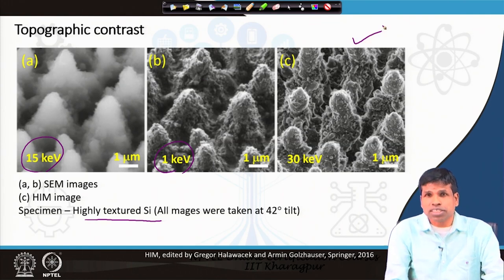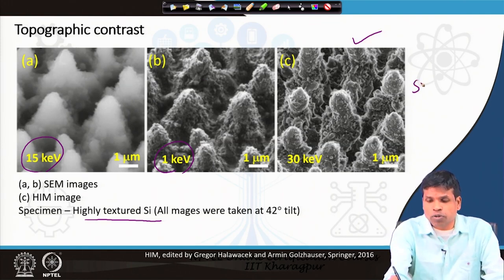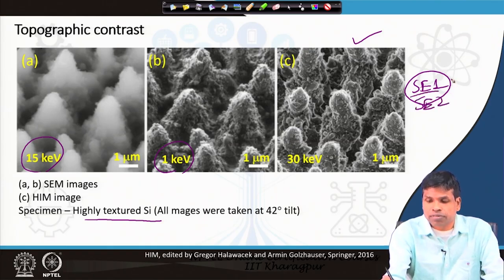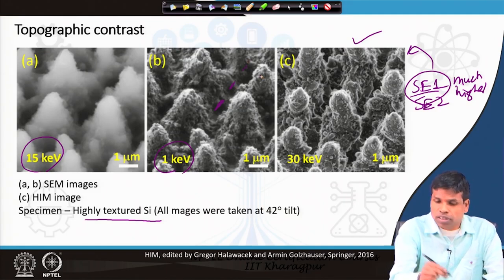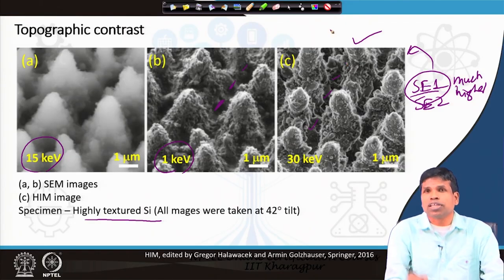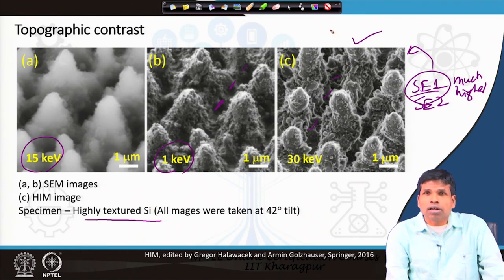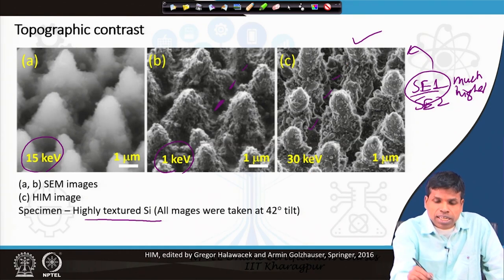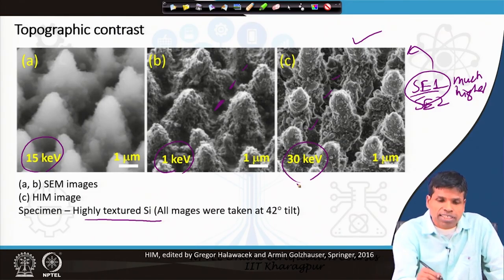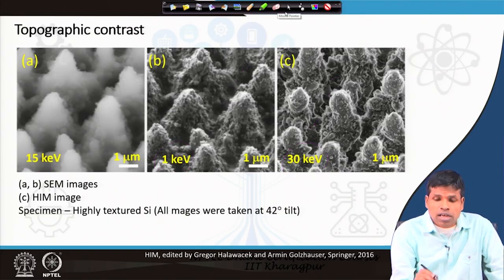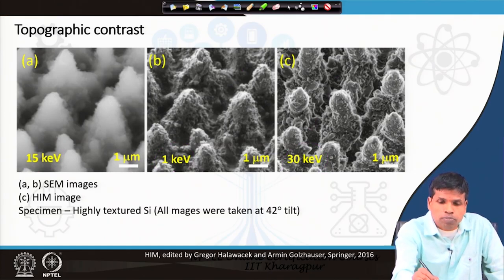The third image is from the helium ion microscope. The surface clarity is much improved because SE1-to-SE2 ratio is much higher, giving not only better resolution but also better clarity. Additionally, the larger depth of field in helium ion microscopy allows using a smaller alpha value — the half-angle of aperture. In helium ion microscopy, a high acceleration voltage is used because the large mass of helium requires higher voltage to achieve sufficient penetration velocity. This topographical contrast is much superior with helium ion microscope compared to scanning electron microscopy.